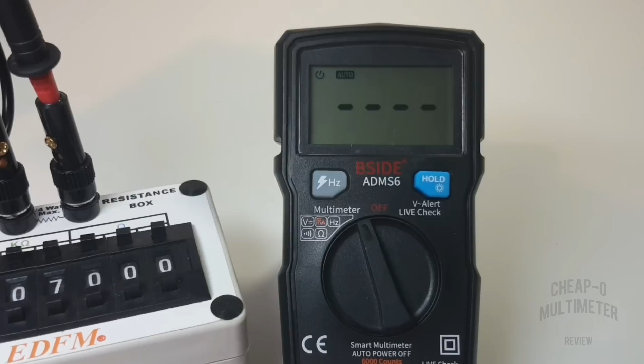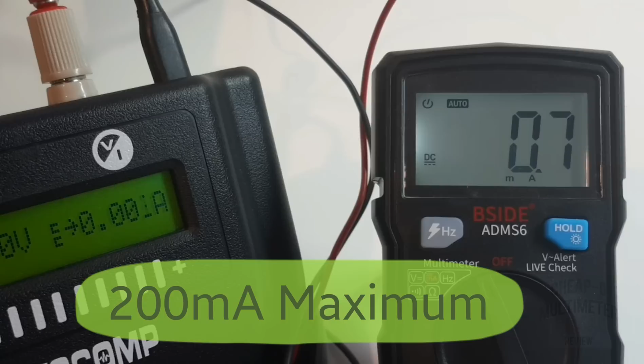Right now we're sitting in milliamp mode around 10 milliamps, and it's a little bit fluttering. Let's take it up. Remember, we have a 200 milliamp threshold. Now we're at 50, 70, 100 milliamps, so far so good, 150 milliamps looking good. This has that resettable fuse, so it should be able to take a little higher than the current limit it's thresholded with. Up to 190 milliamps we're fine, 200 milliamps and we are over limit. So it looks like about 190 is about the threshold. Oh, that was about 198.